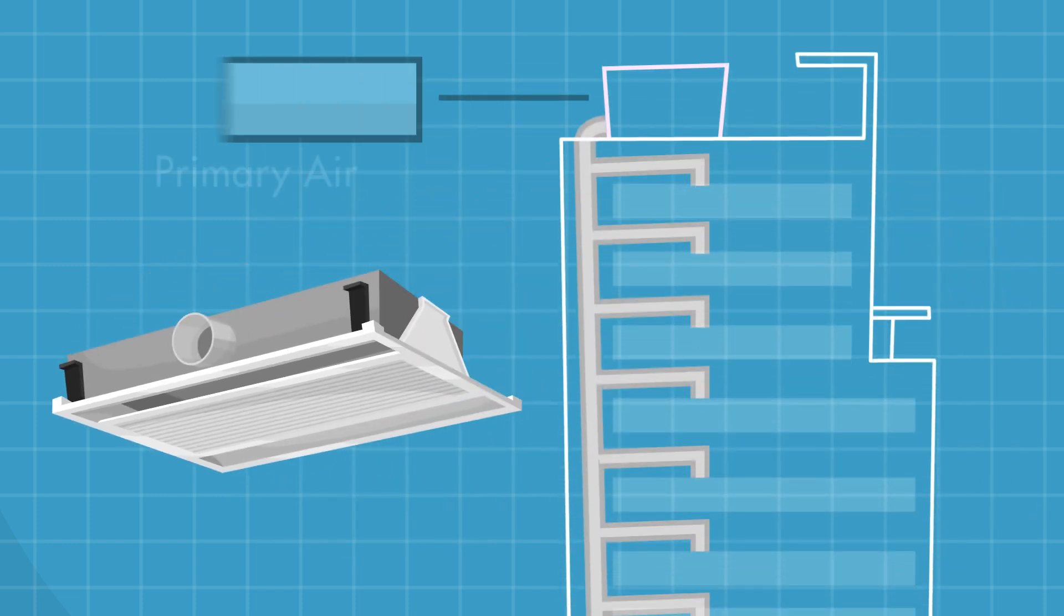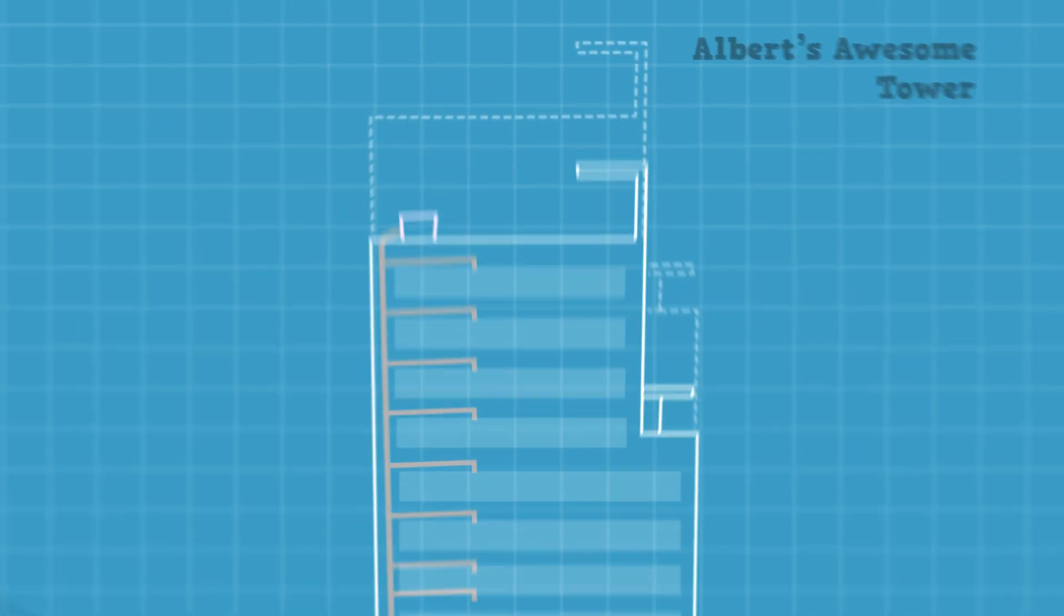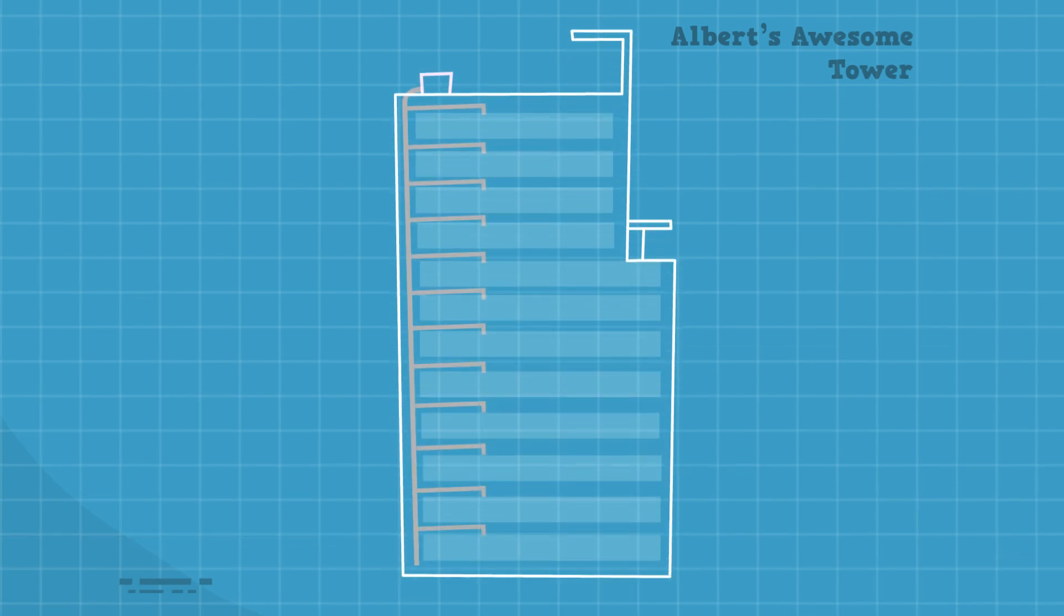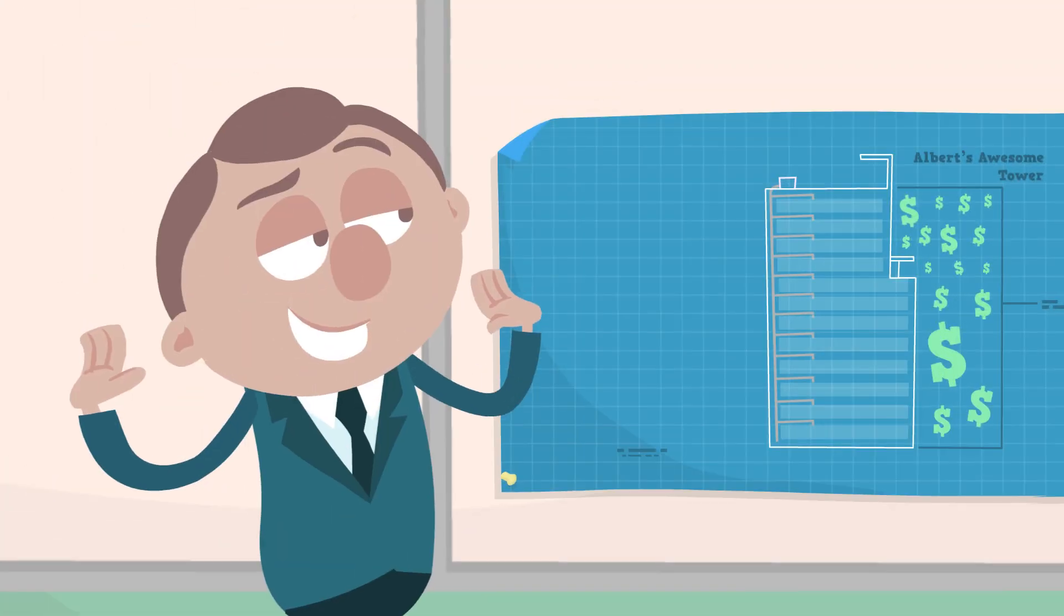Second, while active beams still require dehumidified air from the central plant, they require a lot less primary air. Meaning lower fan power and smaller duct work. This allowed Albert to fit more floors into his building spec. And more floors means more leasable office space.